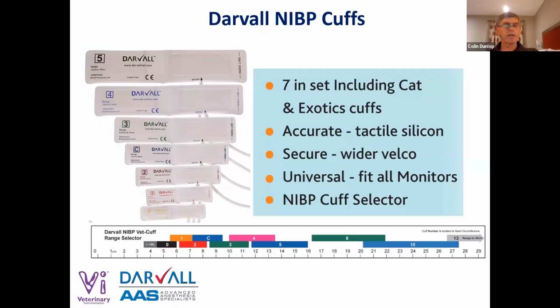Another problem we have in vet medicine is the range of cuffs. We actually make a range of cuffs with 7 cuffs in that range. Why do we do that? We anesthetize a lot of animals down below 3 kilos, and the smallest human cuff is technically designed to measure a circumference bigger than 5 centimeters. If you're talking about ferrets, rats, rabbits, things like that, they're all down here. So we make a cuff that gets down a little bit further. We can't make a cuff go much smaller than that because it doesn't have enough volume in it for the machine to work with.